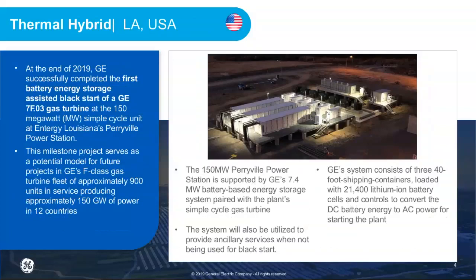Here's a thermal hybrid we commissioned at the end of last year. It's a 7.5 megawatt hour energy storage system that provides black start for a 150 megawatt power station, a 7F03 gas turbine, for Entergy at their Perryville power station. They were doing this primarily for cost avoidance, keeping a number of very old diesel generators alive that were utilized only for black starting this asset. They were able to get a rate of return on this job, and when it's not being used for black start, it will be used for ancillary services in that market.